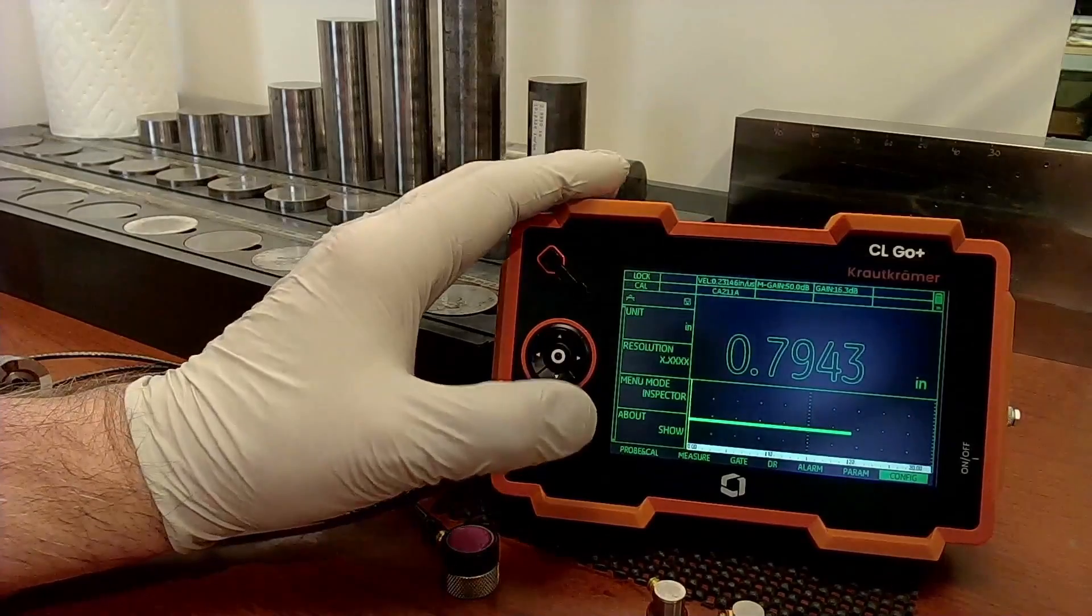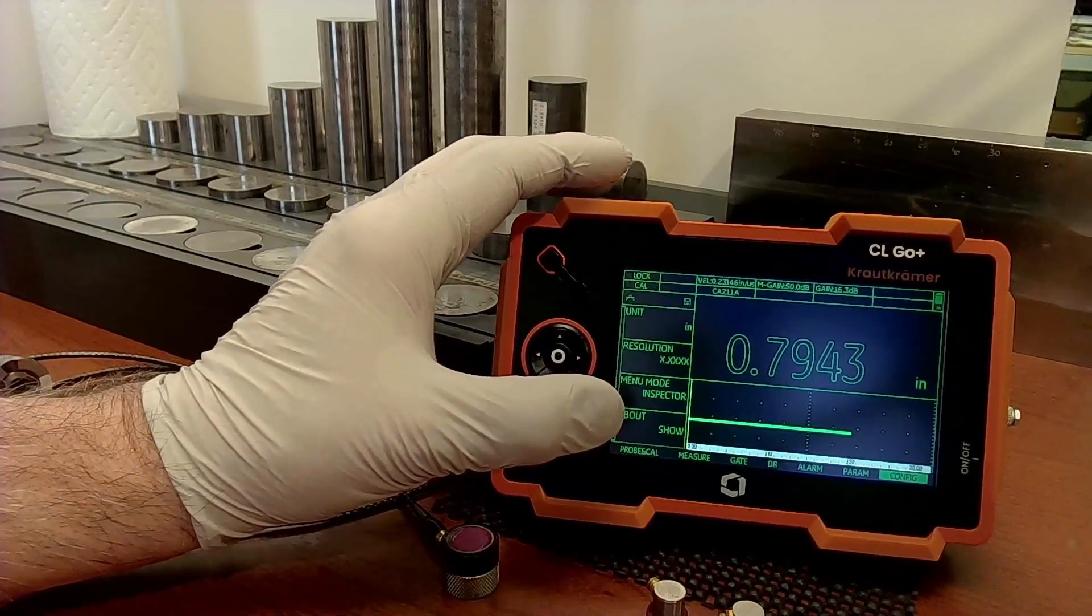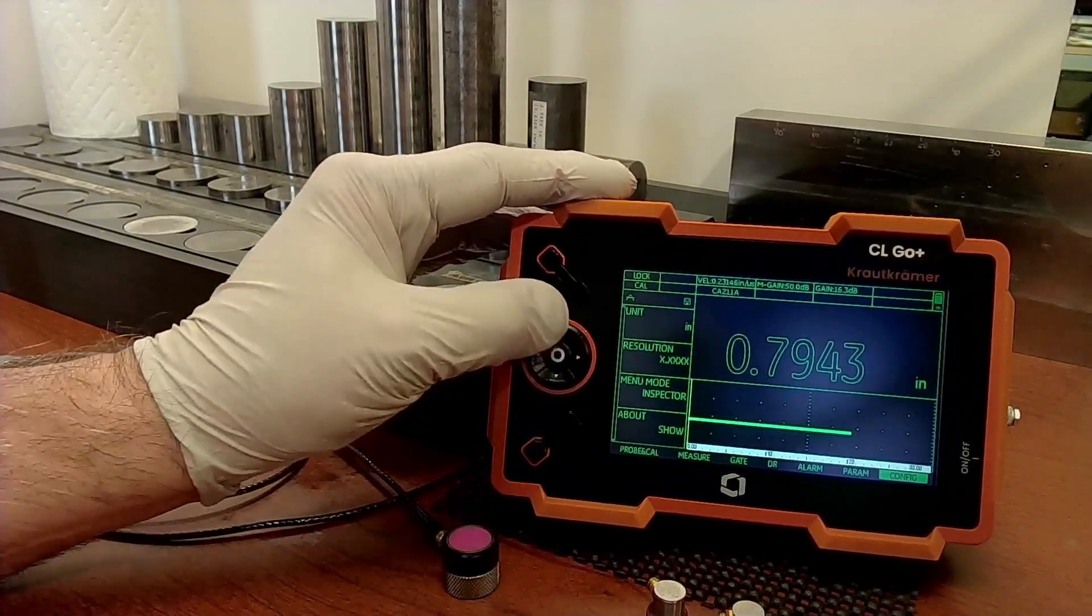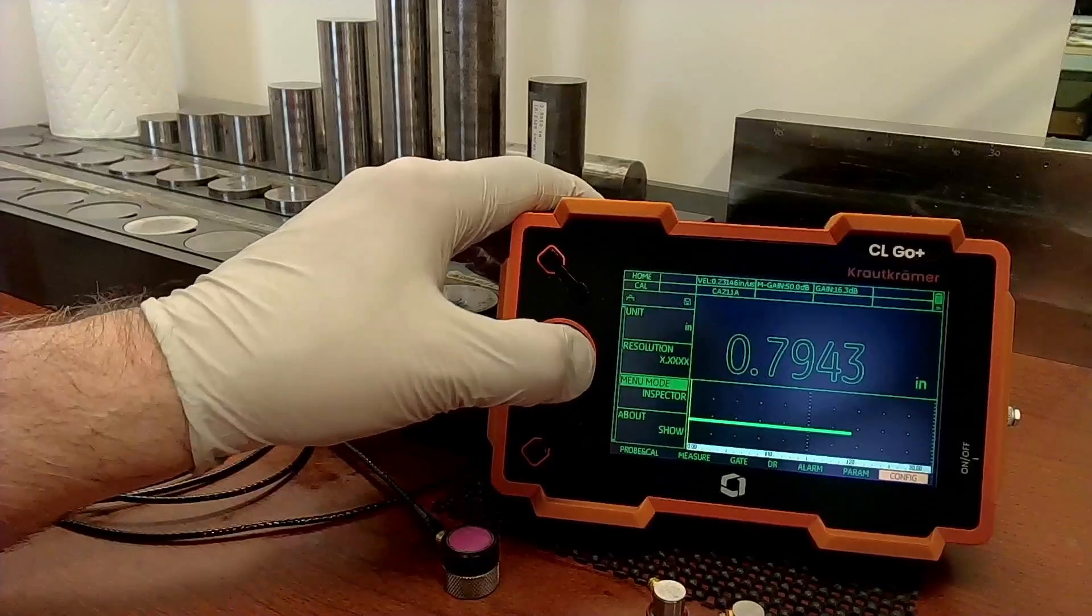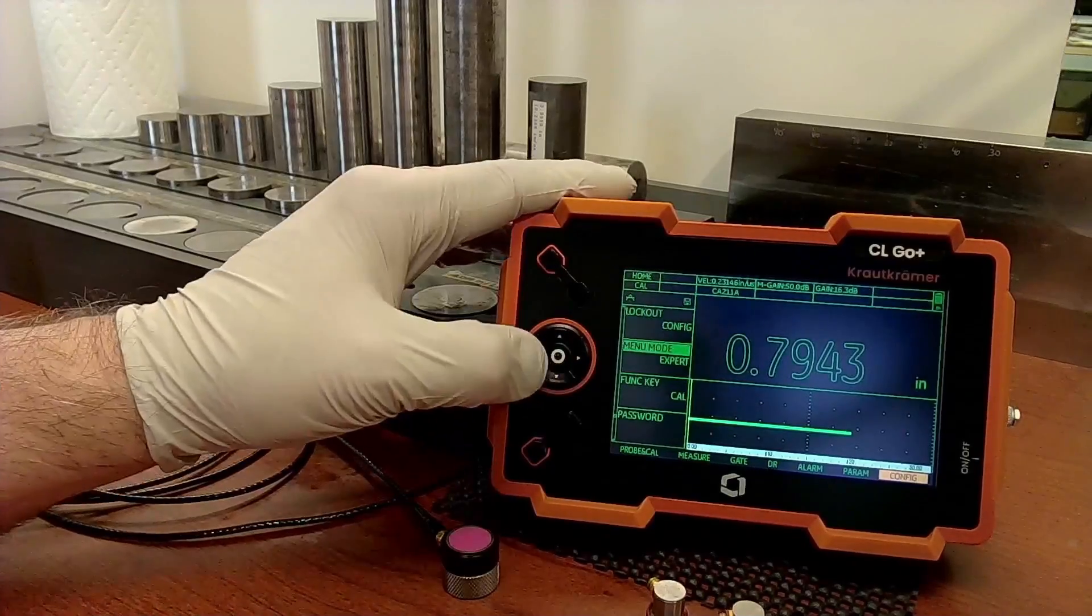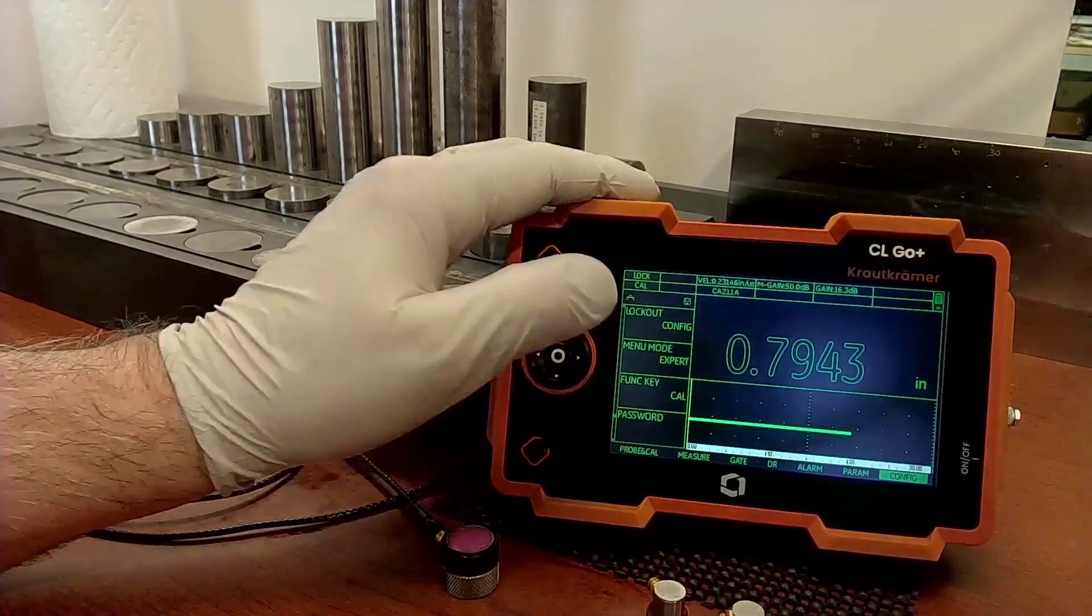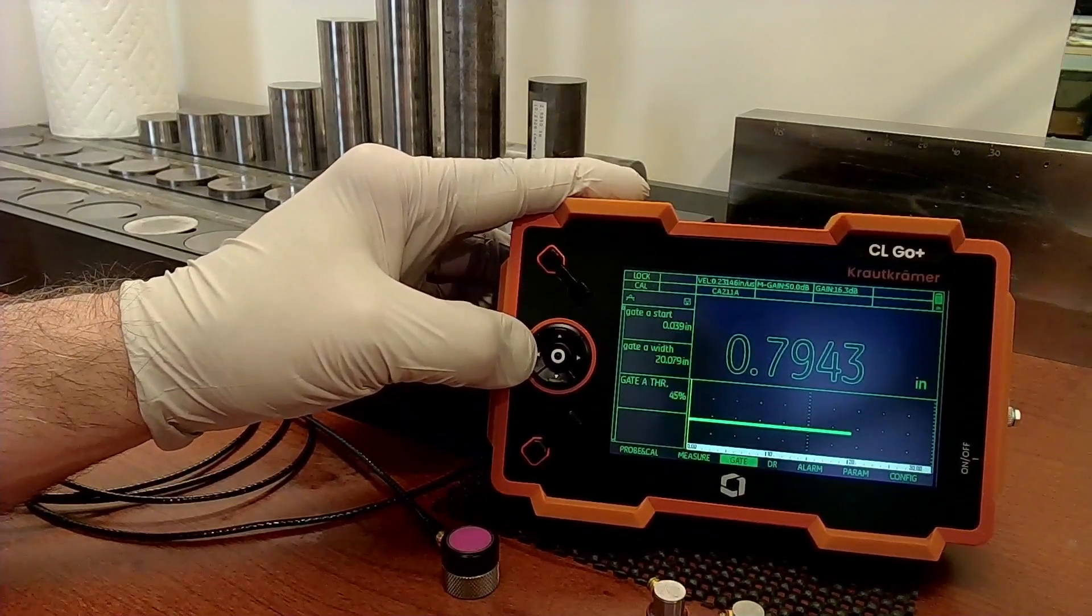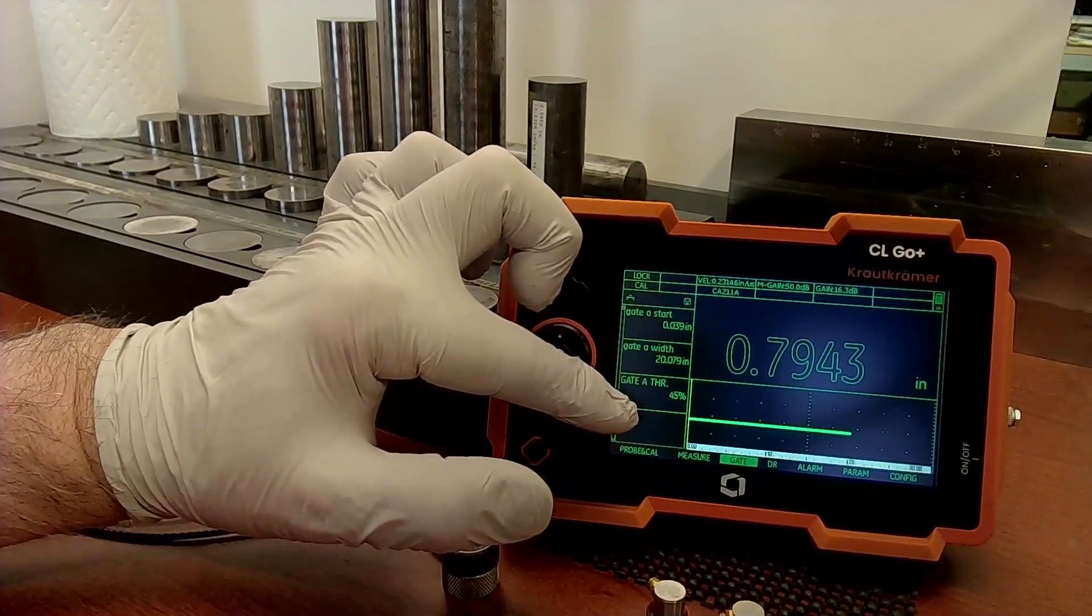Because all of the gating and gain control is available to an expert user for adjustment, if we come to the config menu and activate the expert mode, now in expert mode, there are a great many more menu items available to the user. For instance, in inspector mode, the gate menu is completely blank.